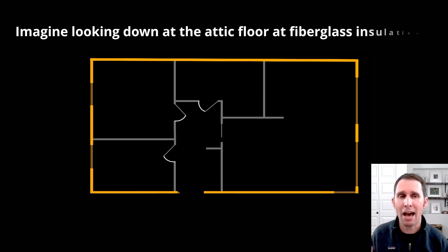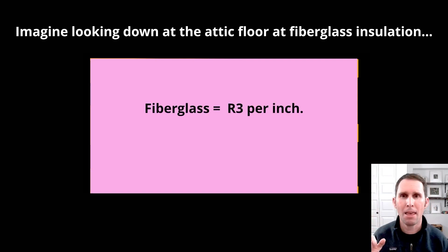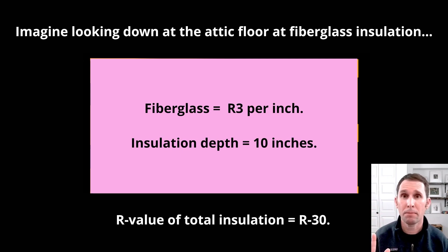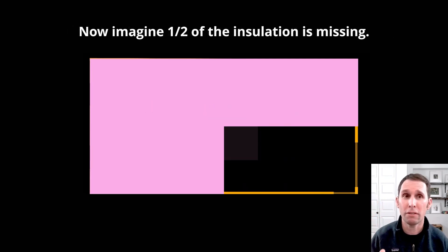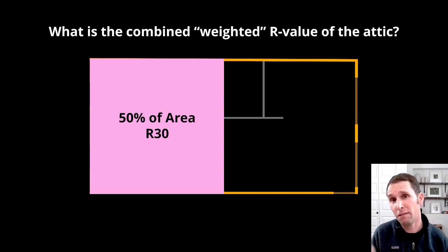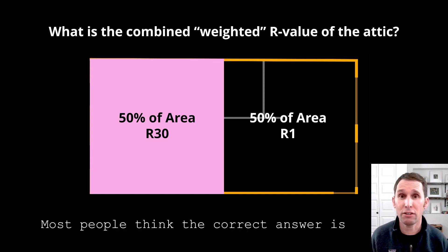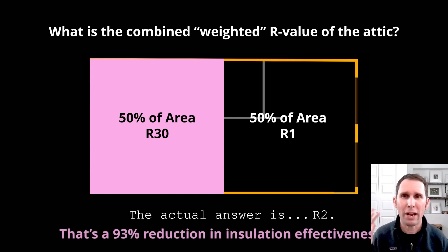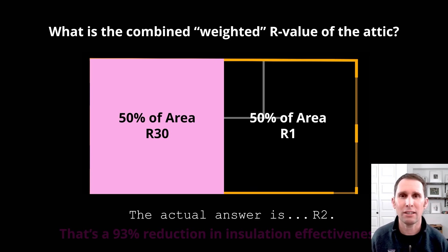Imagine looking down at an attic floor. That's the ceiling, but you're looking down from above. And it's got fiberglass, which is R3 per inch of insulation at a level of 10 inches deep. So, the total R-value of that insulated area is R30. Now, imagine again looking at this area and we remove half of that insulation. So, what do you think the combined or weighted R-value of this attic floor is? So, 50% has R-value of R30. The other 50%, let's just say that's a piece of drywall, has an R-value of R1. So, most people think the correct answer is the average of the two of them, about R15. That would be inaccurate. Believe it or not, the actual answer is R2. Mind blown. Wait, that's a 93% reduction in insulation effectiveness. How is that possible?